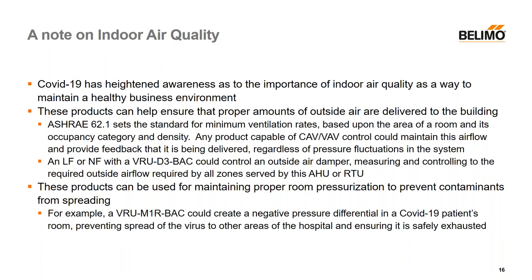Separate from airflow, when talking about room pressurization, you can also use room pressurization as a technique to mitigate the flow or spread of contaminants. The example I'd give is that a VRU-M1R-BAC could create a negative pressure differential in a COVID-19 patient's isolation room. When you create that negative pressure differential, if somebody opens the door to the corridor, air flows from the corridor into the room — not the other way around. You won't have potentially contaminated air moving out into the corridor and spreading the virus. The contaminated air would be safely exhausted somewhere with no occupancy. So there are a few different techniques you can use to help improve indoor air quality.